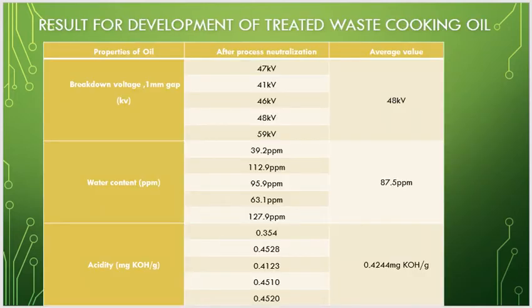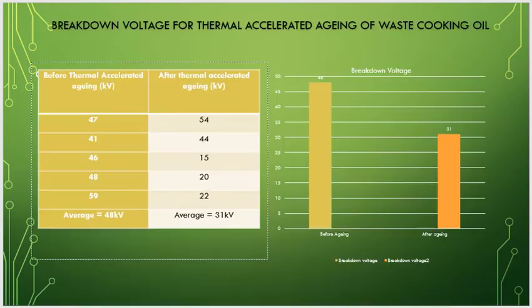For the results for the development of treated waste cooking oil, for breakdown voltage, the average value is 48 kV. For water content it is 87.5 ppm. For acidity it is 0.4244 mg KOH per gram. And this is the result for breakdown voltage for thermal accelerated ageing of waste cooking oil before and after. We can see before aging is 48 and after aging is 31.